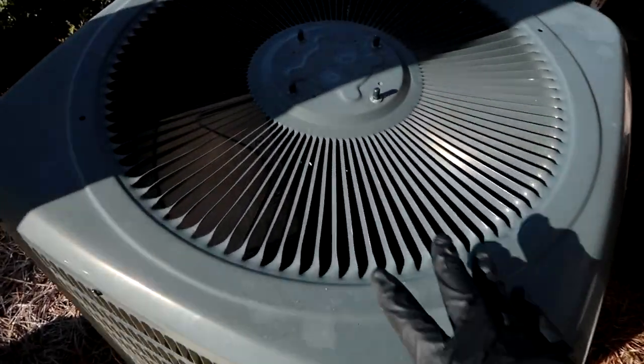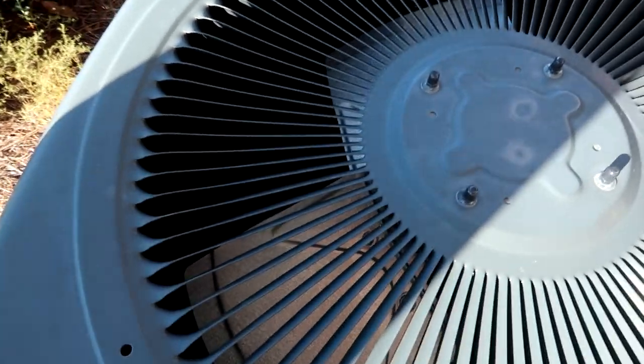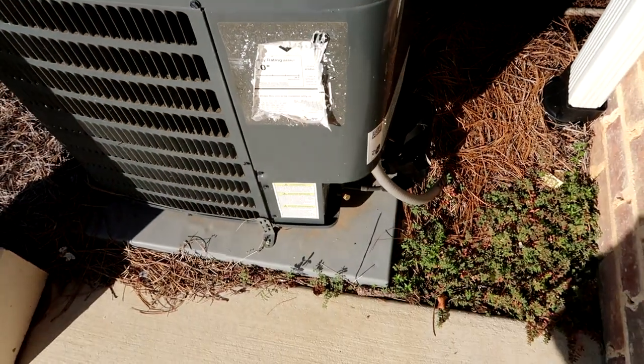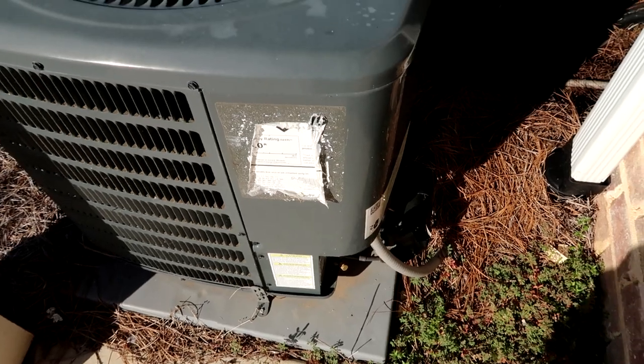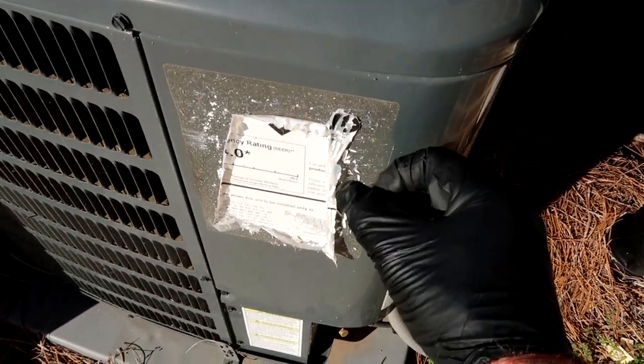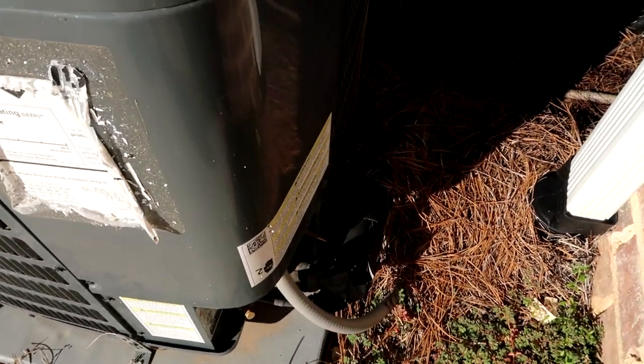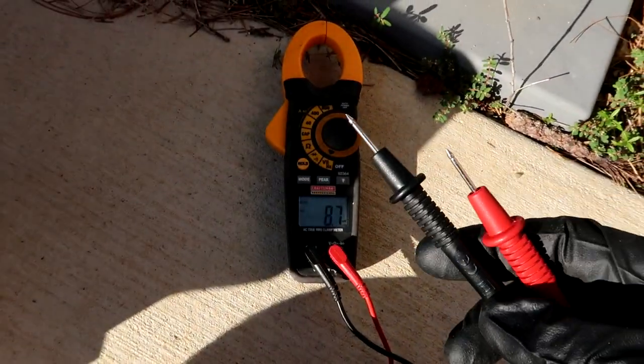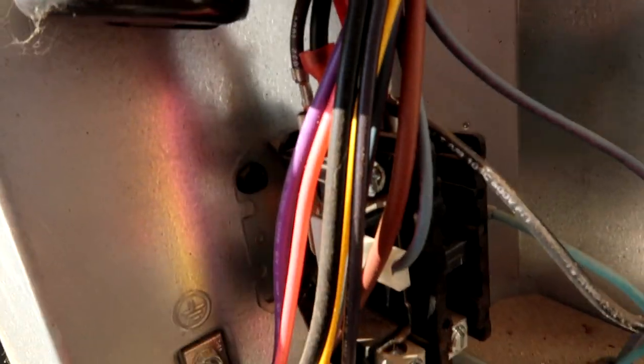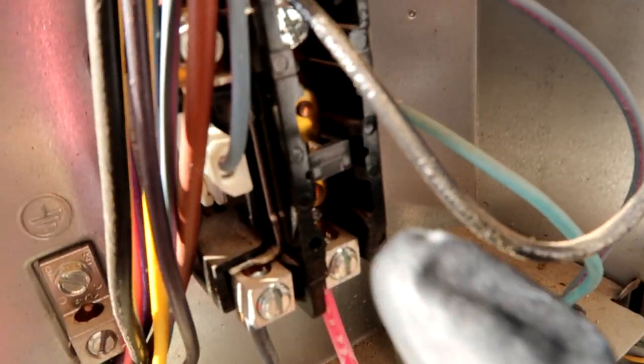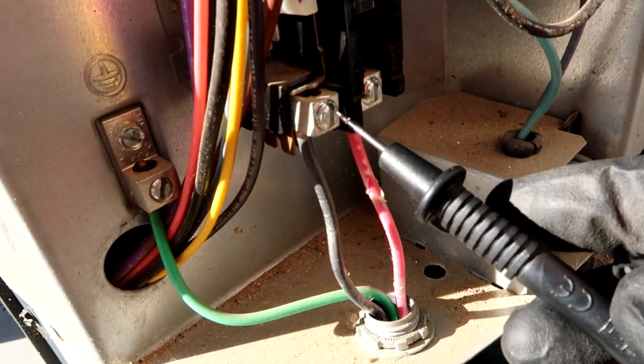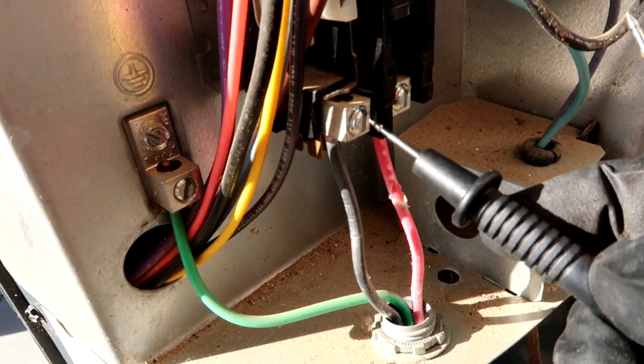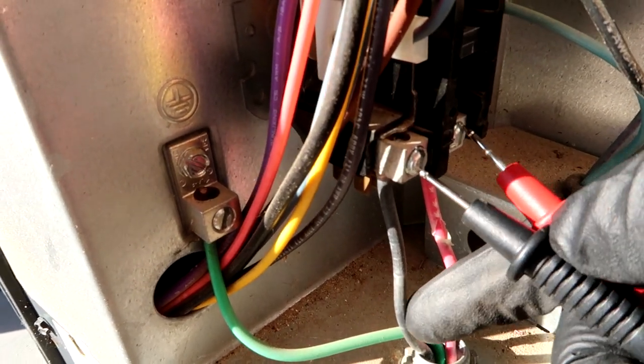Here's our unit right here. Nothing's on at all - no fan, no compressor, nothing. Taking the cover off to see what's happening. Broke out the multimeter. I see the contactor is made, it's pushed in. Let's see if we've got high voltage.